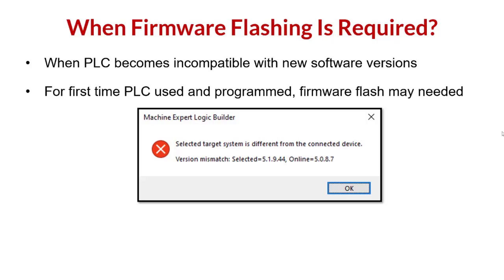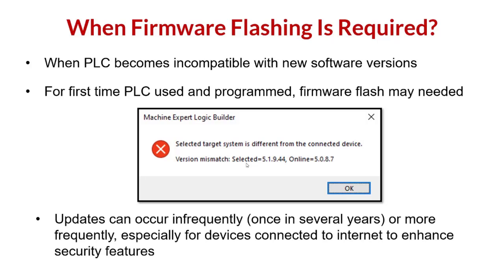If you try to program the PLC for the first time, you may get an incompatibility message. This is what happened in our case with the Schneider Modicon M241 — the online version, meaning the hardware actually connected to the computer, is not compatible with the PLC version included in the software. In this case, we have to update the firmware installed in the PLC. This update process can occur infrequently, like once every several years, or more frequently if the PLC is connected to the internet.